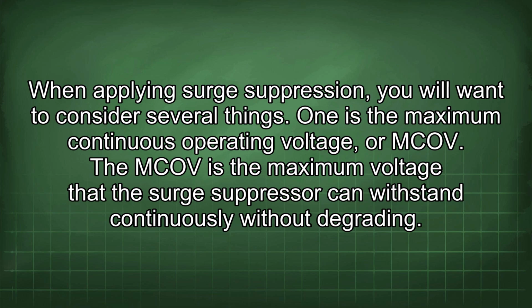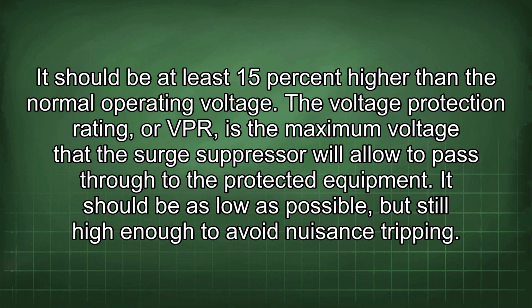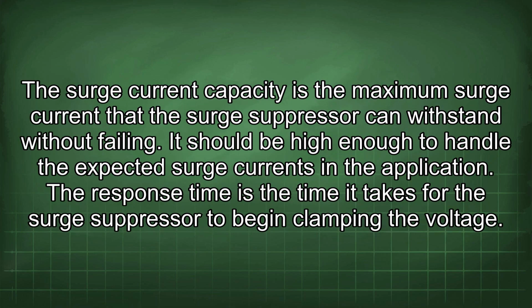One is the maximum continuous operating voltage, or MCOV. The MCOV is the maximum voltage that the surge suppressor can withstand continuously without degrading. It should be at least 15% higher than the normal operating voltage. The voltage protection rating, or VPR, is the maximum voltage that the surge suppressor will allow to pass through to the protected equipment. It should be as low as possible, but still high enough to avoid nuisance tripping. The surge current capacity is the maximum surge current that the surge suppressor can withstand without failing. It should be high enough to handle the expected surge currents in the application.